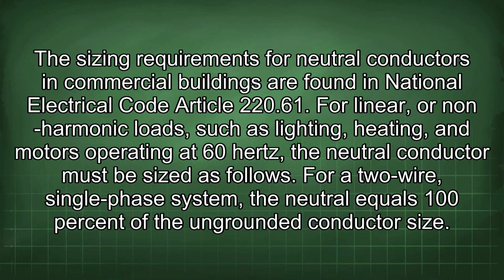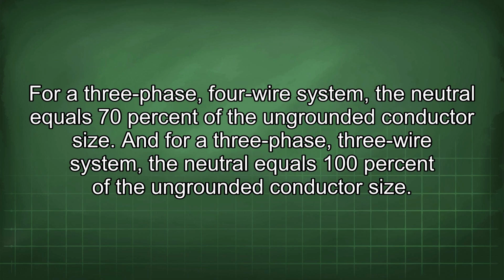The sizing requirements for neutral conductors in commercial buildings are found in National Electrical Code Article 220.61. For linear or non-harmonic loads such as lighting, heating, and motors operating at 60 Hz, the neutral conductor must be sized as follows. For a two-wire, single-phase system, the neutral equals 100% of the ungrounded conductor size. For a three-phase, four-wire system, the neutral equals 70% of the ungrounded conductor size.